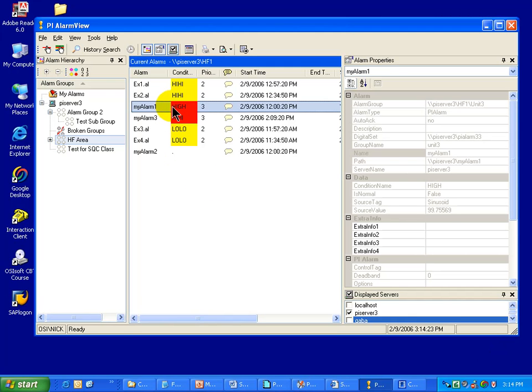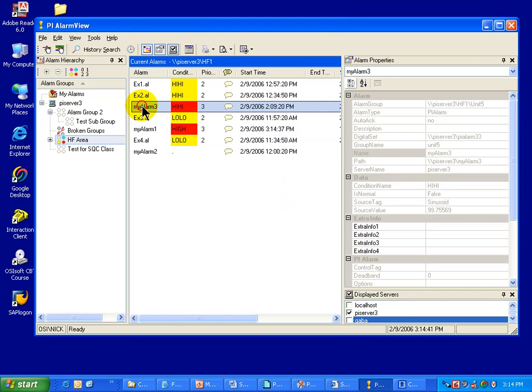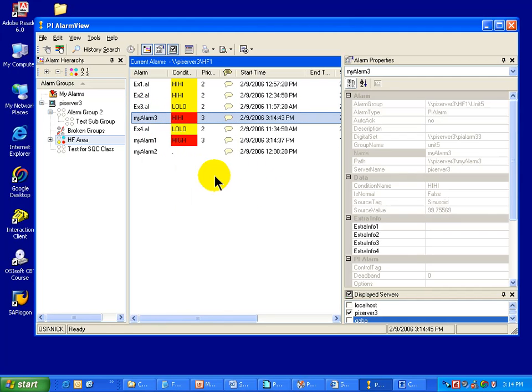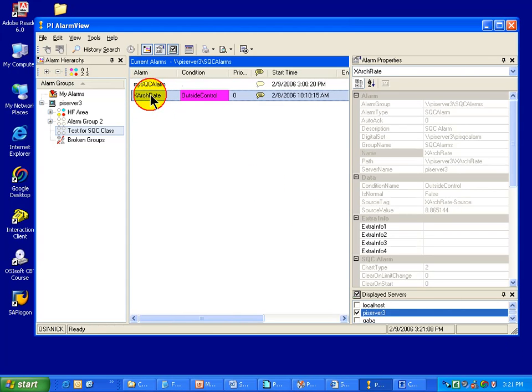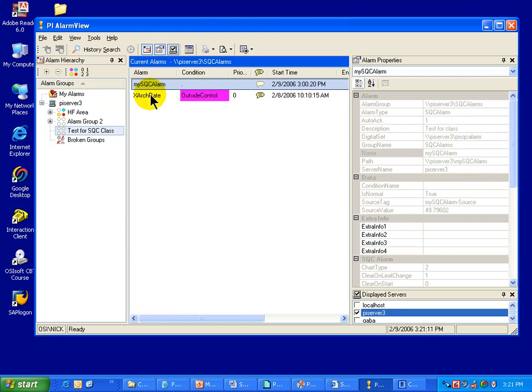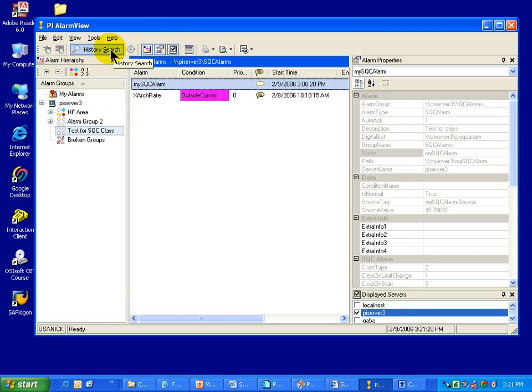When working with alarms, if an alarm triggers and requires acknowledgement but goes out of alarm before it is acknowledged, we consider it a missed alarm. You can acknowledge an alarm by selecting it and choosing Acknowledge — when you do that, it will no longer be blinking in the Alarm View interface. There is also a History Search available on a tag-by-tag basis where you can select multiple tags. For example, I've selected MySQC Alarm and can click the History Search button.